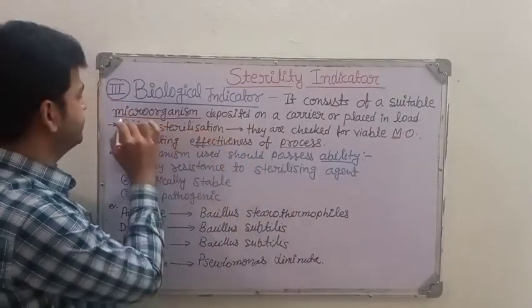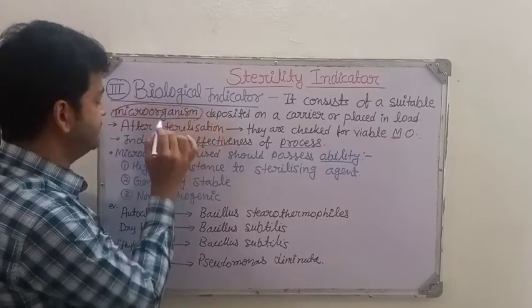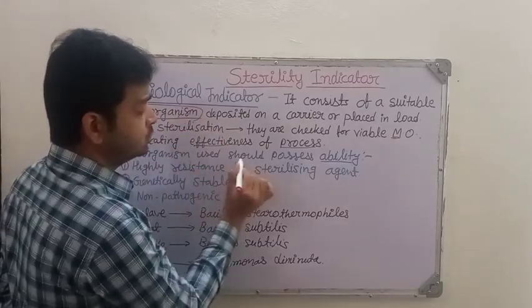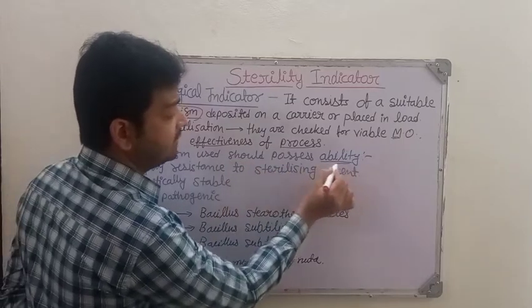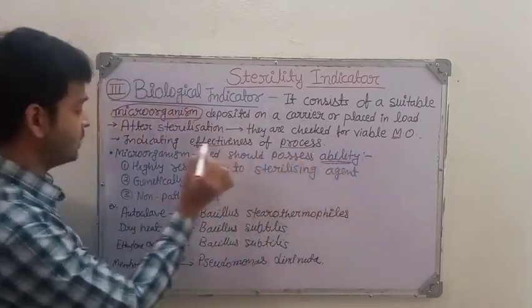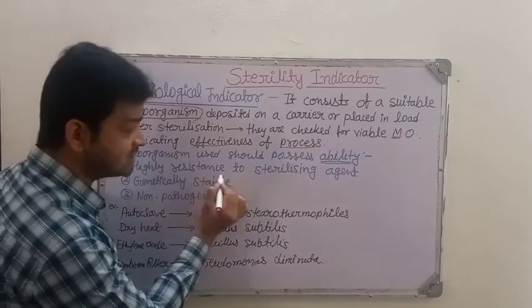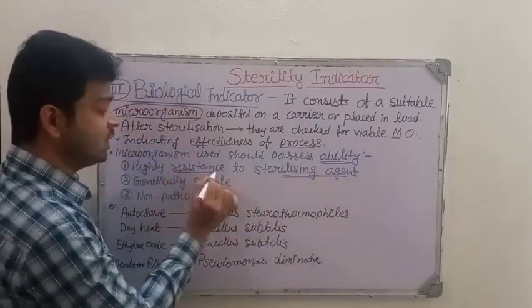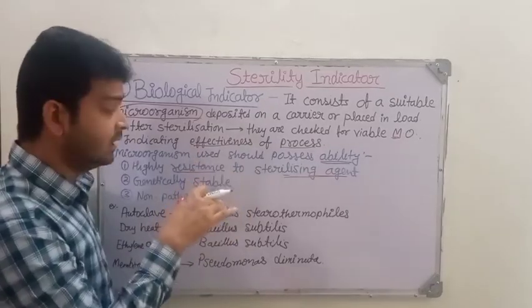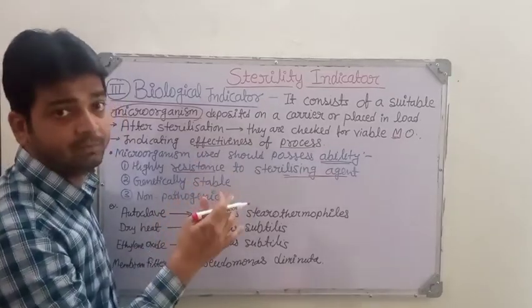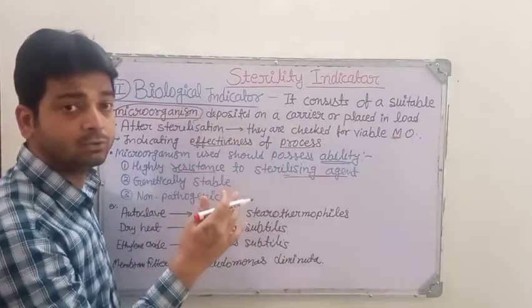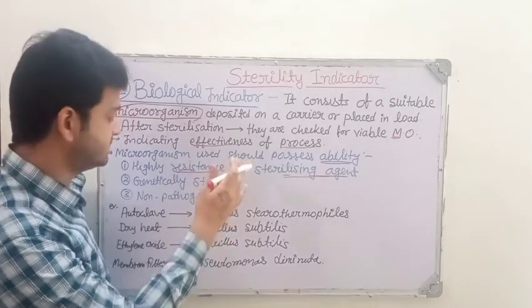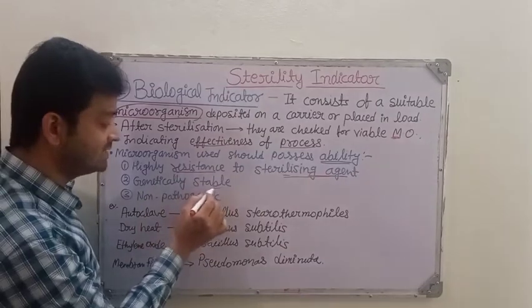The microorganisms which we are using as a biological indicator should possess certain abilities. What ability should they have? They should be highly resistant to the sterilizing agent. If they are not resistant, they may die and we will not be able to recover them or know what happened during sterilization. Also, genetically they should be stable and should not be manipulated.